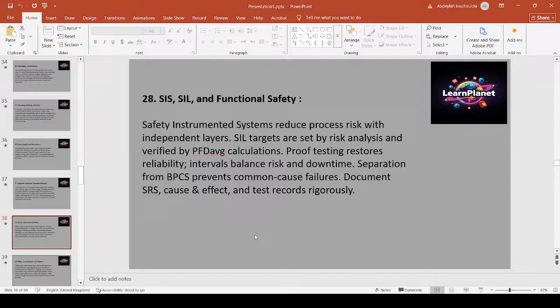SIS, SIL, and functional safety. Safety instrumented systems reduce process risk with independent layers. SIL targets are set by risk analysis and verified by PFDavg calculations. Proof testing restores reliability; intervals balance risk and downtime. Separation from BPCS prevents common cause failures. Document SRS, cause and effect, and test records rigorously.